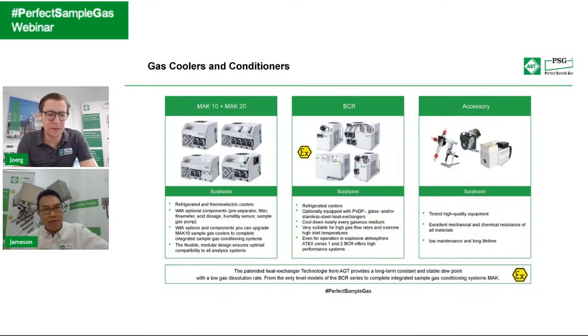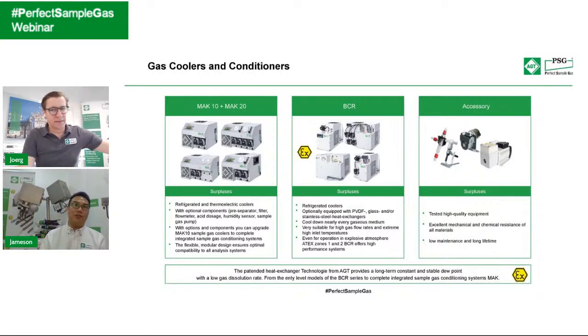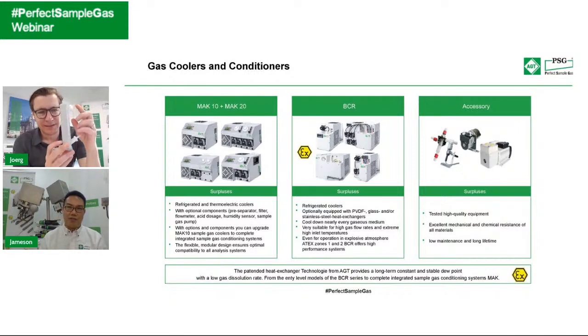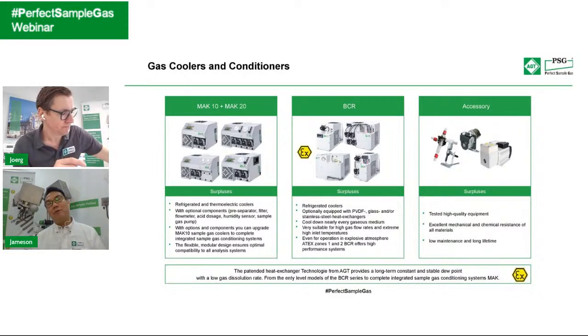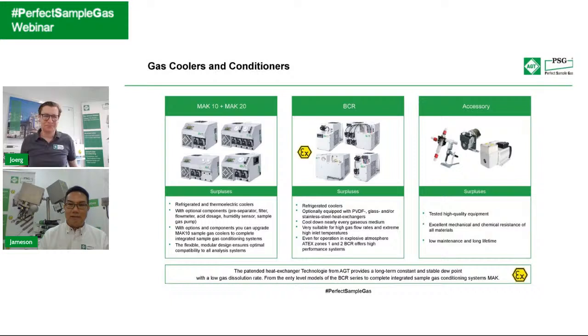The second reason is that every exchanger is limited to a flow capacity. For example, for ours it would be 2.5 liters for one exchanger, just one of the models. We have so many models. What happens if you select only one exchanger because of competition, because you want to cut costs, and you buy a gas cooler with only one exchanger which can handle 2.5 liters per minute, and your sample pump is sucking 5 liters per minute? What happens is overloading. The speed of the flow going through is much faster than the gas cooler is able to cope with. This is the second phenomenon.